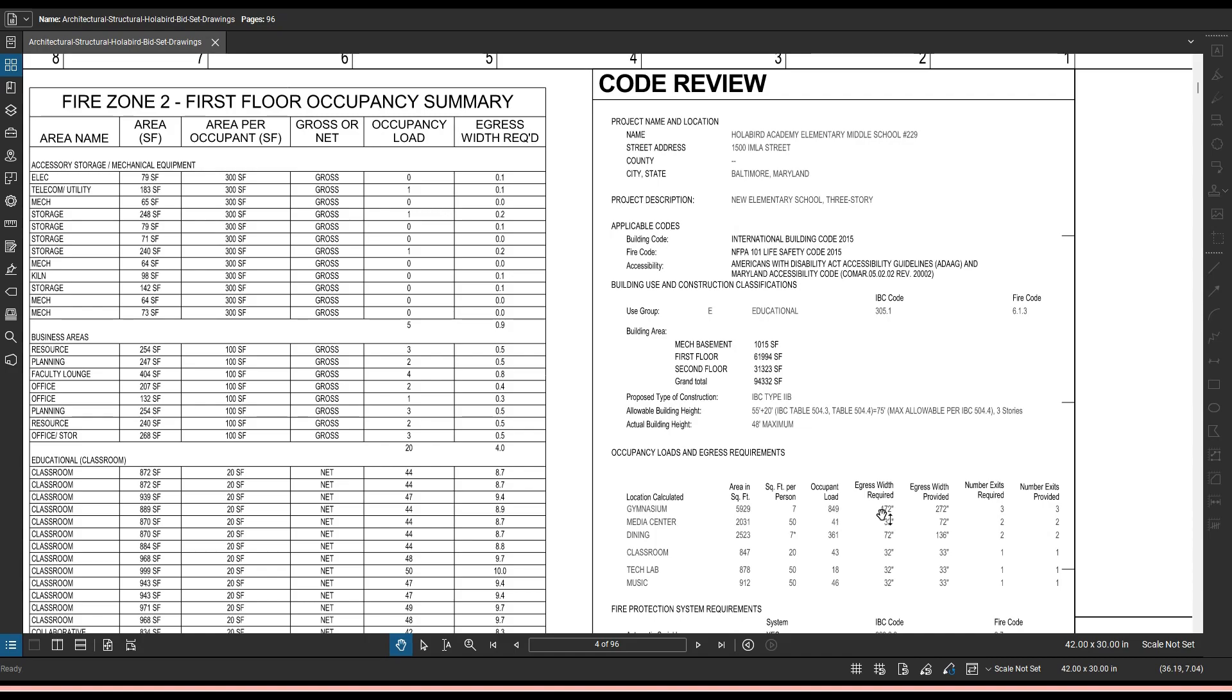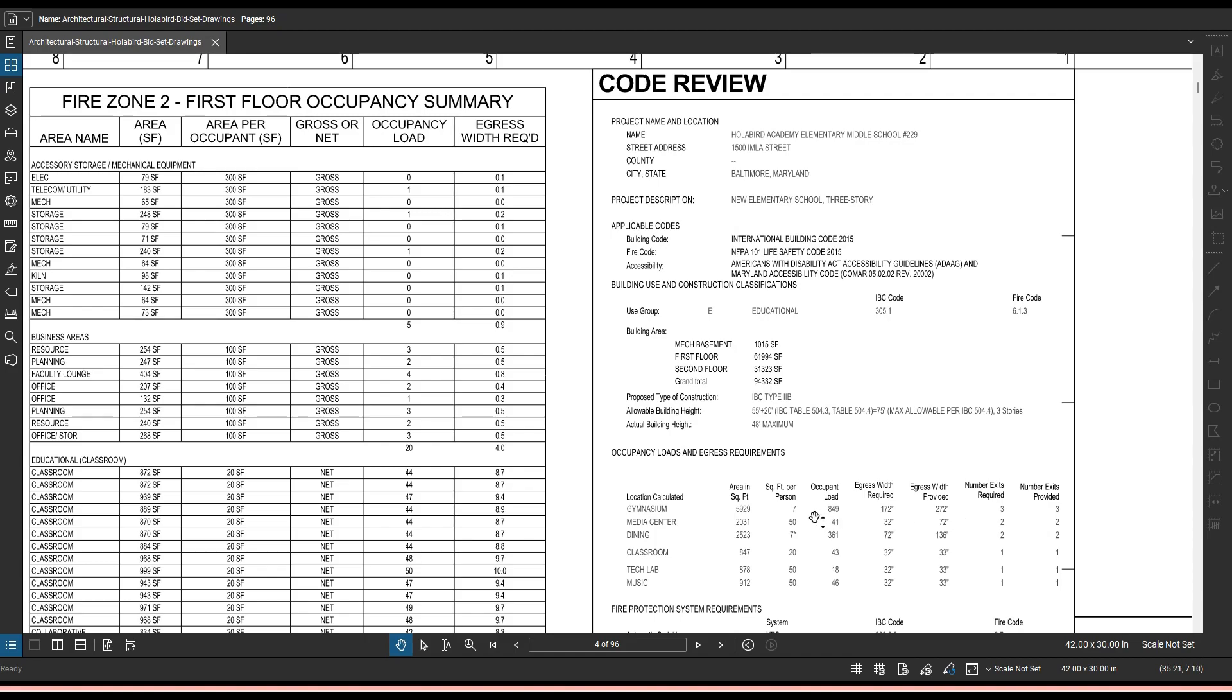The egress width required means that any egress, any hallways leading to an exit need to be at least 172 inches wide in order to fit the amount of people through there. Now the egress width provided, meaning what was designed for this building is 100 more inches, 272 inches. The number of exits required in the gym, that's based off of the occupancy load and the area. There's three exits that are required and they provided three.